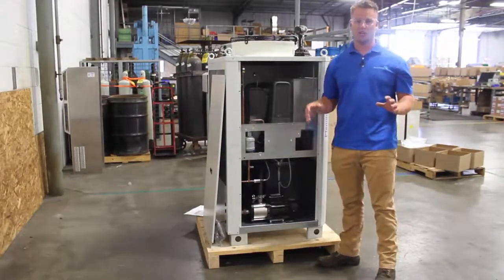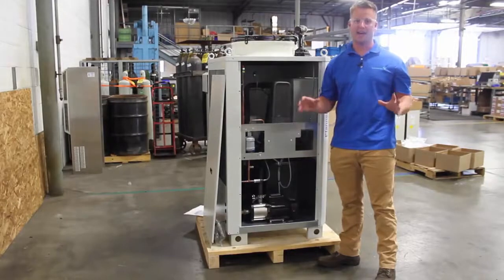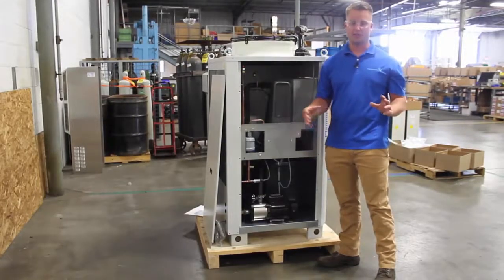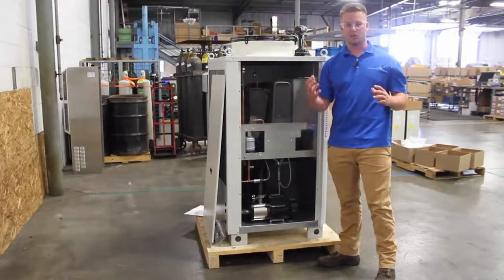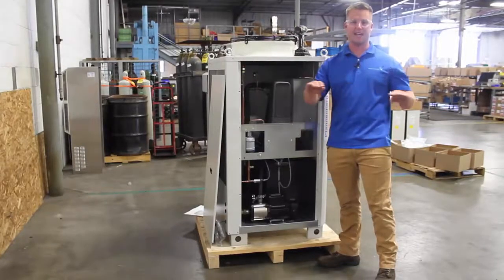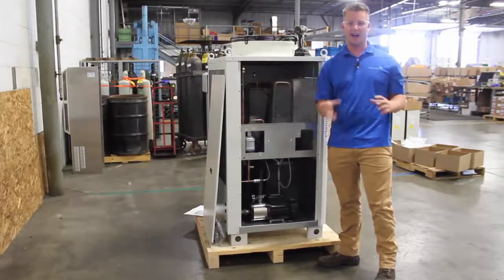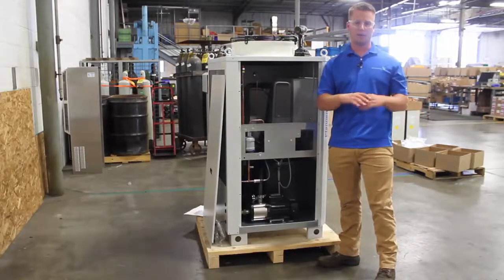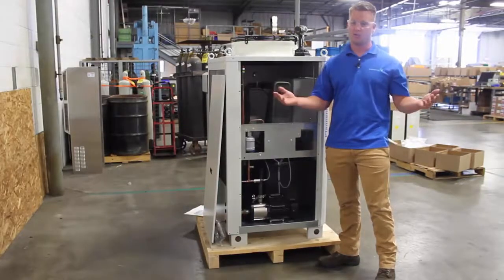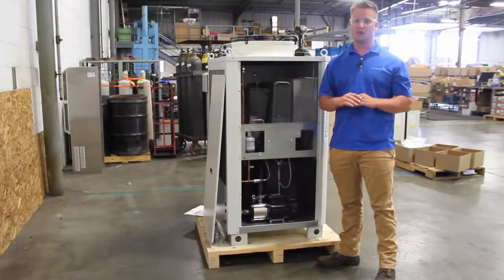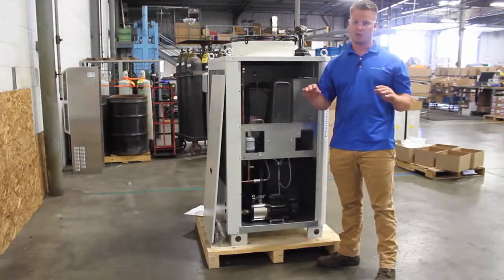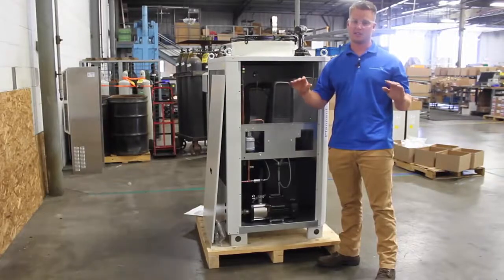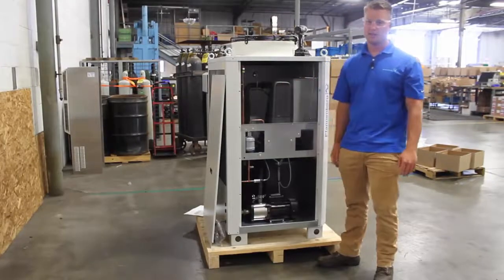So this chiller is equipped standard with a hot gas bypass setup. What that means, if your system is getting close to the set point and you want to maintain your compressor staying on, the hot gas bypass valve will open and we'll put an artificial load on the compressor. What does this do? Make sure your compressor stays running for longer periods of time to increase the service life of the compressor. It stops your on-off cycling.